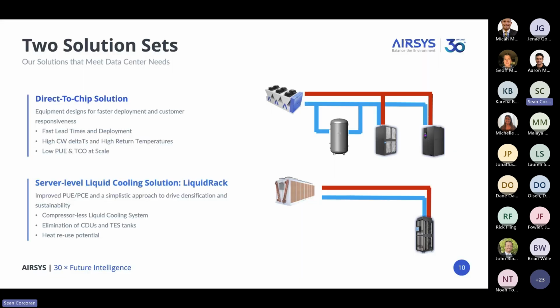We have two solutions to meet the data center needs, right? First, the direct-to-chip solution, where the equipment is designed for faster deployment, faster lead times, higher chilled water delta Ts, and low PUEs and total cost of ownership. And then we have the server level liquid cooling solution, which is the liquid rack, which is looking to improve the PUE and the PCE, working hand in hand to help in the densification and sustainability. The compressorless liquid cooling system eliminates CDUs and thermal energy storage tanks and has tremendous heat reuse potential.